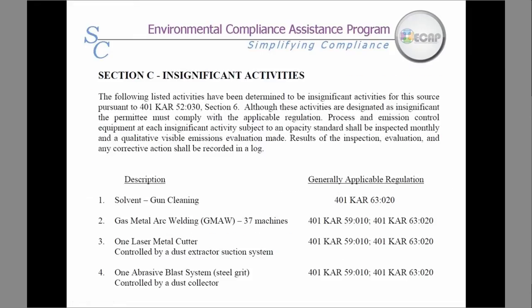Section C lists the insignificant activities. Insignificant does not mean they can be forgotten about — you may still have requirements to report them in your EIS and list them on your semiannual and annual reports. As stated in the permit text, the permittee must comply with regulations, and processes and emission controls subject to the opacity standard shall be inspected monthly with qualitative visible emissions recorded in a log. Also, those keeping a 12-month rolling total must include solvents used for cleaning guns listed in insignificant activities.